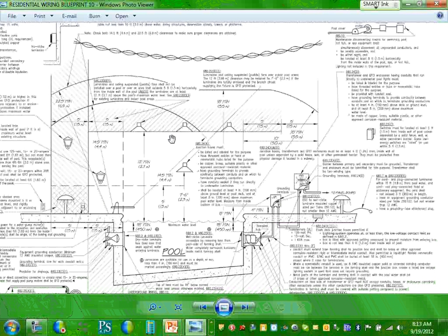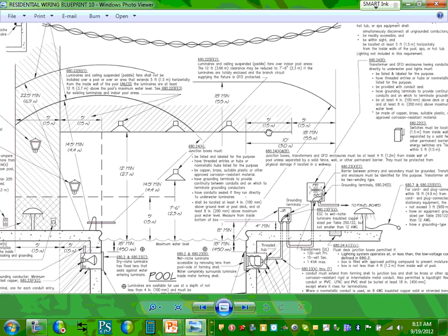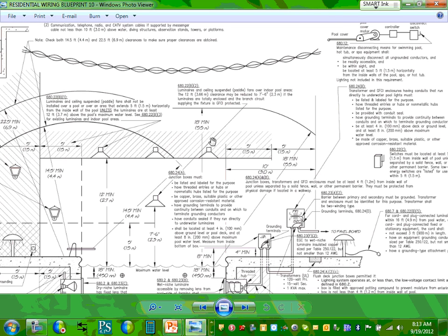We move our poles 5 feet away from the swimming pool, and we make our poles maybe 8 foot high, and we GFCI that circuit. That will get you the requirement. GFCI that circuit. Can I have thumbs up, Chad? Put them at 8-foot pole, GFCI the circuit, and put them further away, 5 feet, and you're good to go. So that's your light for GFCI.